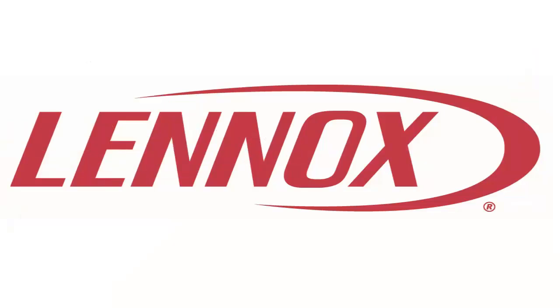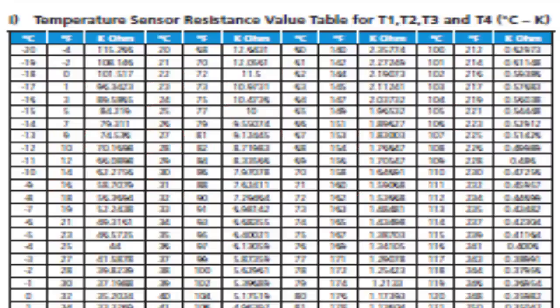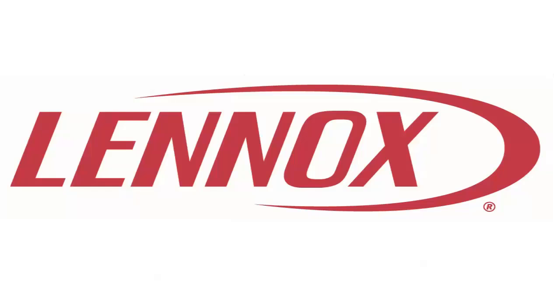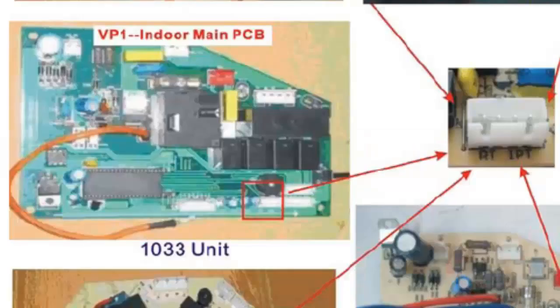7. If you have the unit's manual, compare the measured value with the sensor's characteristic table. If it does not match, replace the sensor. 8. If the error persists, visually inspect the electronic board controlling the sensor for faults. Consider replacing the electronic board involved if the problem continues.